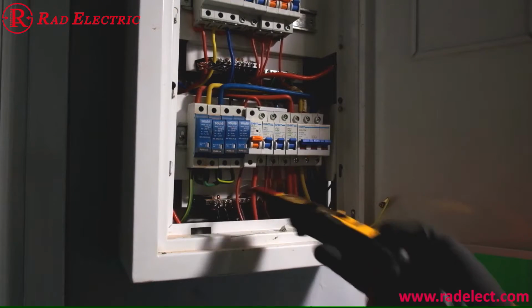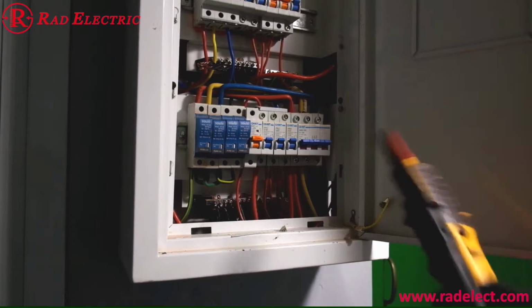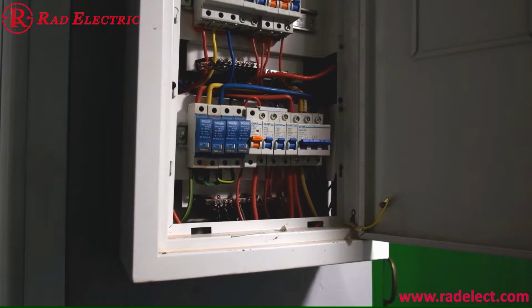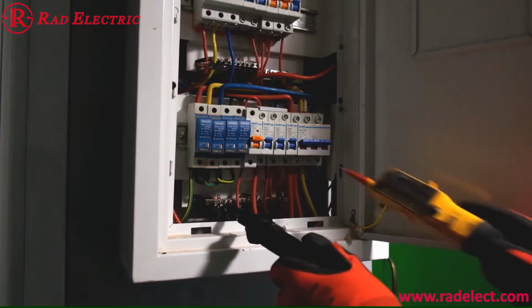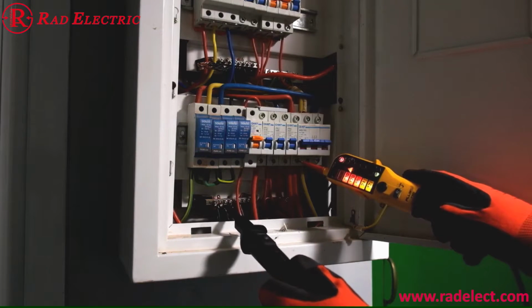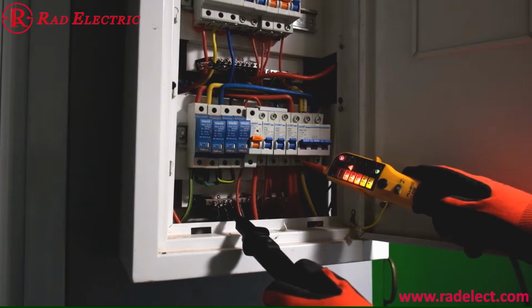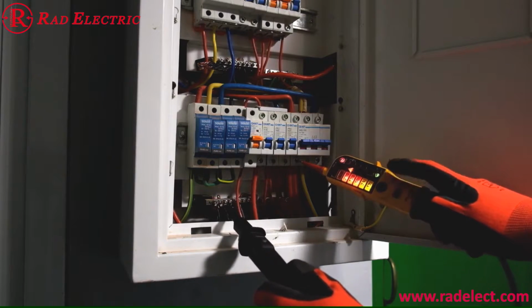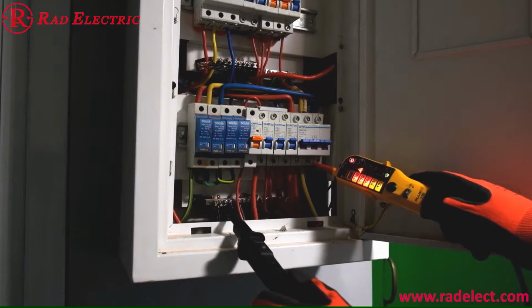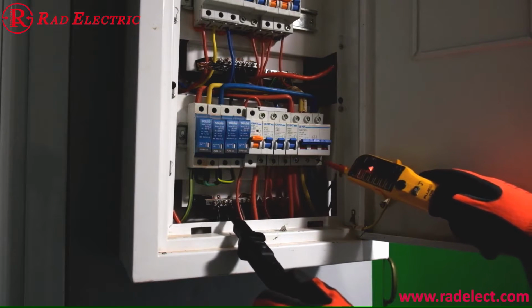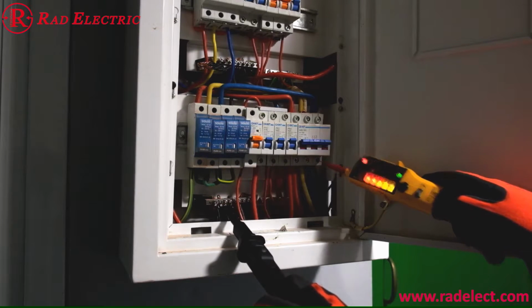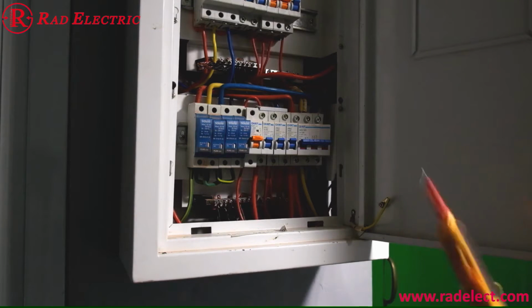Down here we have our neutral bar, so between the neutral bar and there we have 230 volts here in South Africa. Now just to check that, we can connect across here to here, and there you'll have your 230 volts display showing up, and we can see a rotation left. On this one, again same, and on this one again same. They're all 230 volts, and the phase to phase is about 400 volts here.